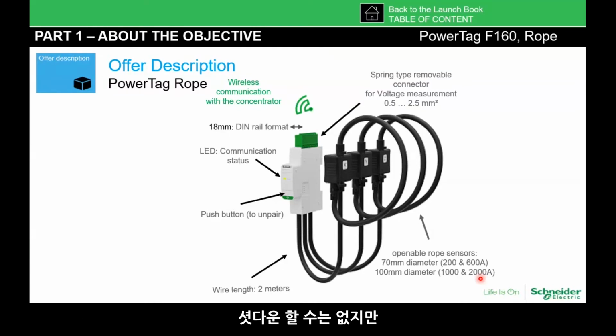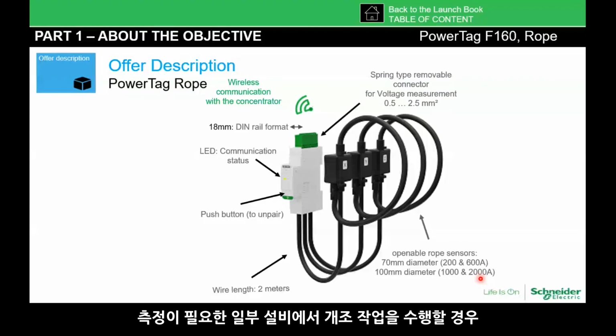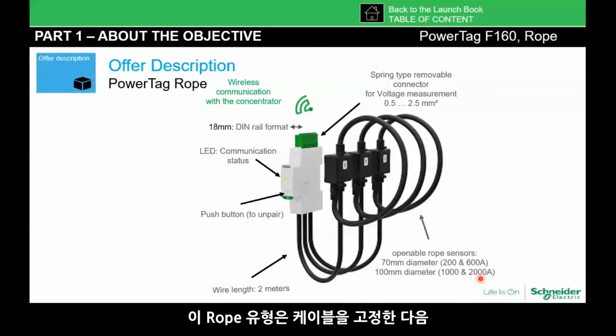So it's very flexible when you're doing retrofit work on installations that you cannot shut down, but still need to do some measurement. You find this rope type, just clamp it around the cables, install the meters, and you can start metering. Most of these power tags use wireless communication, so you don't really need to worry about running comms cable from one device to another—basically everything is wireless to a gateway, and then from the gateway, just one cable out to the Ethernet backbone of the system.